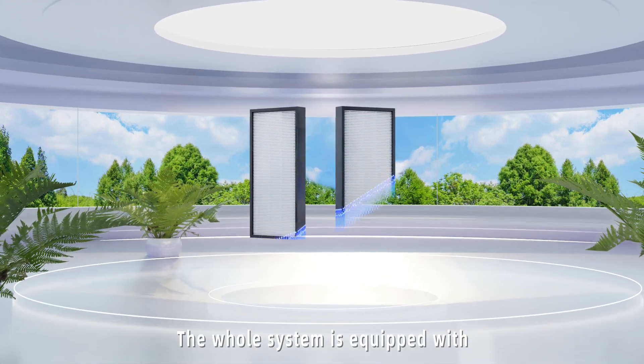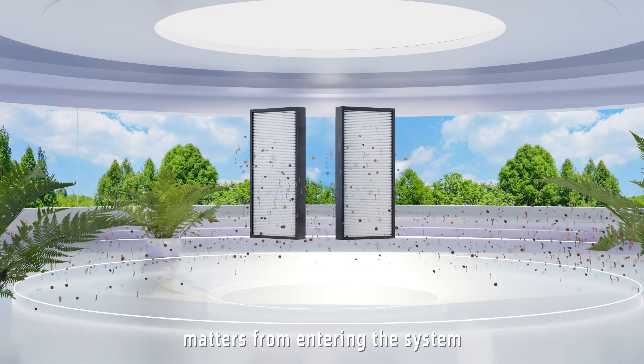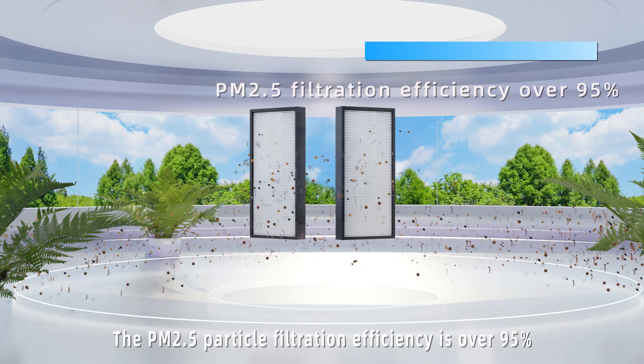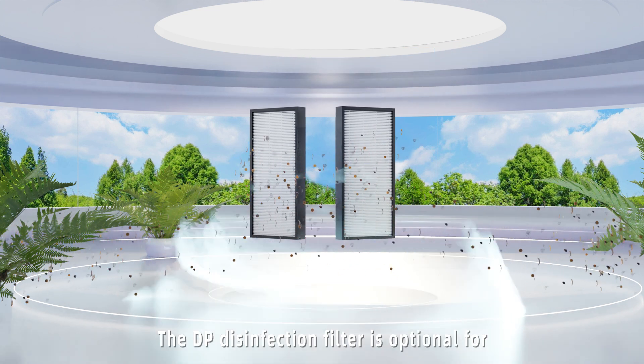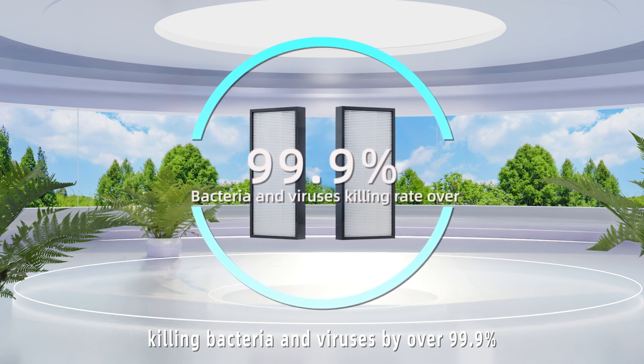The whole system is equipped with G2 filters to stop large particles from entering the system, and an F8 filter to further purify the air. The PM2.5 particle filtration efficiency is over 95%. The DP disinfection filter is optional for killing bacteria and viruses by over 99.9%.